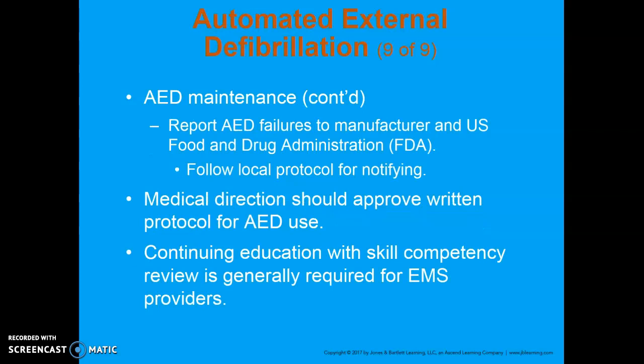You want to report any failures to the manufacturer and to the FDA. There should be a protocol for how you do that. And then make sure that you let your supervisors and others know as well, because you need to take that out of service. Medical direction should approve a written protocol for AED use. You should already have that in place and you should know what it is. You should always submit for quality improvement, which reviews every incident that an AED is actually used, regardless of what the patient's outcome was. Quality improvement may end up bringing you in to talk about your use and how it went, things that you could have done better.